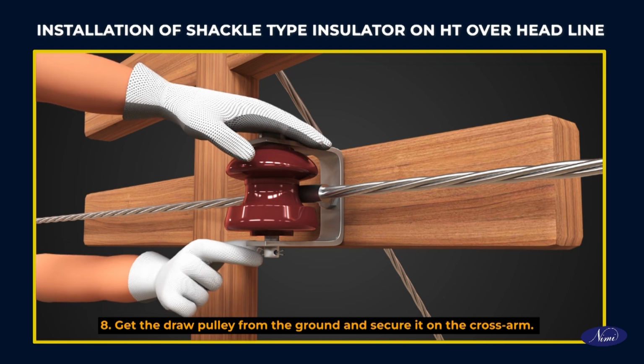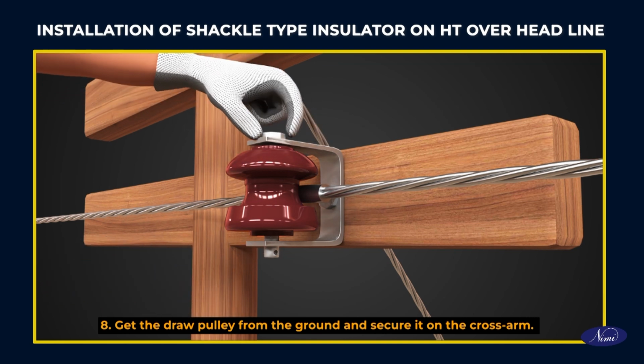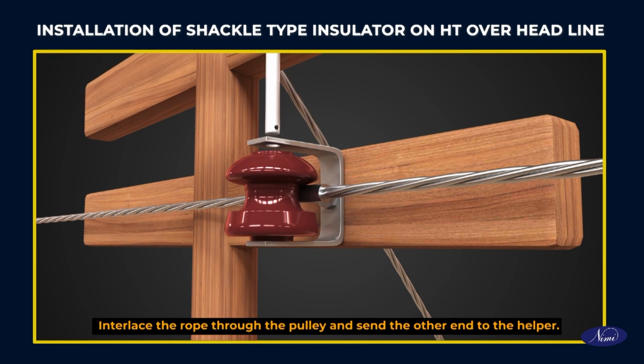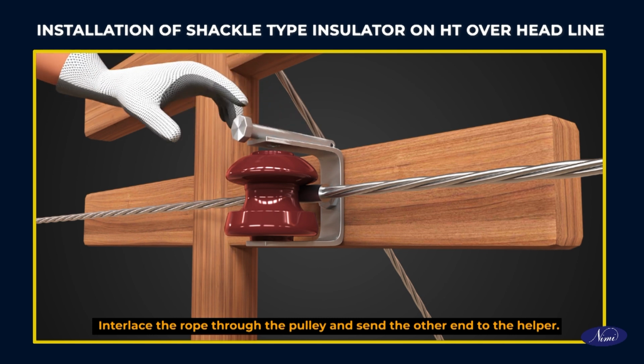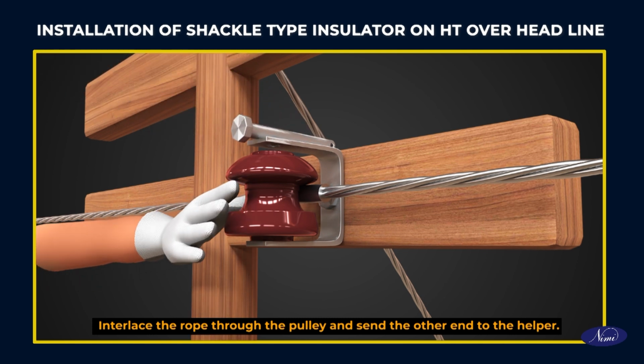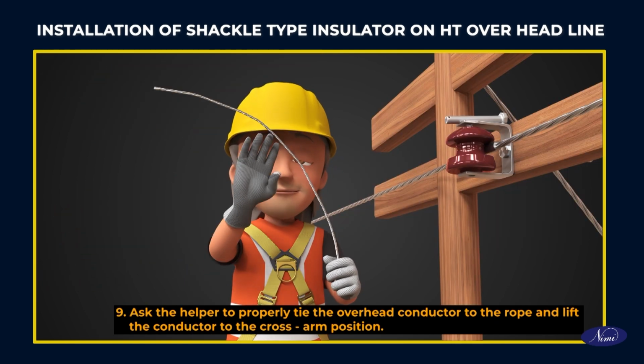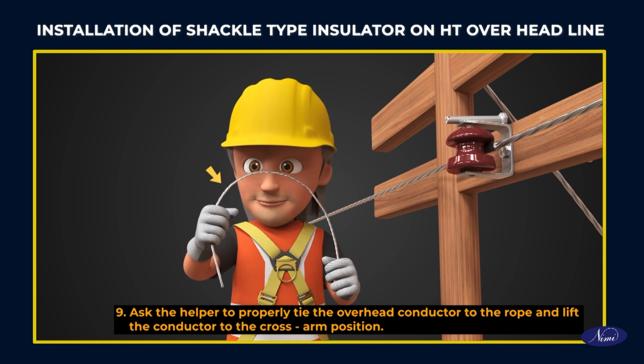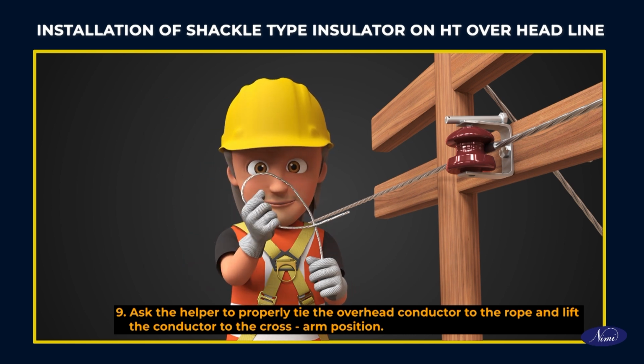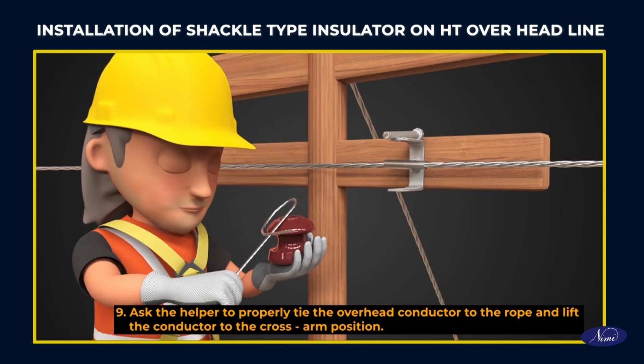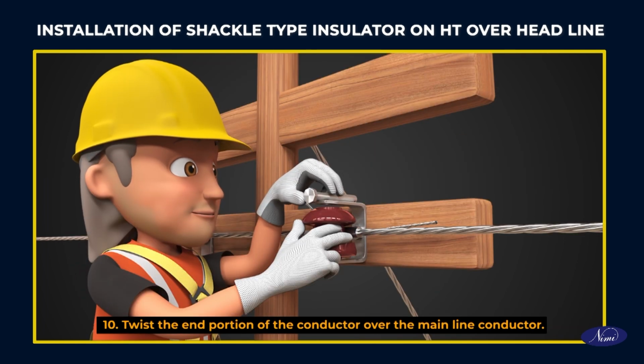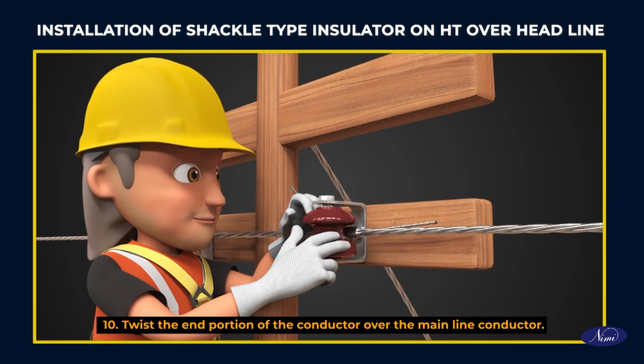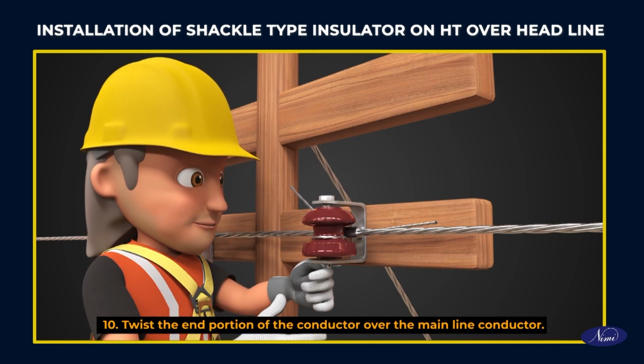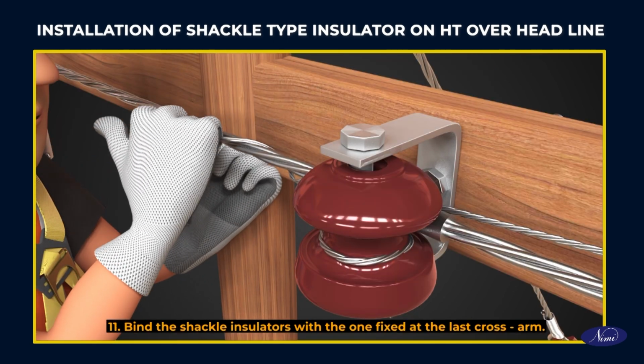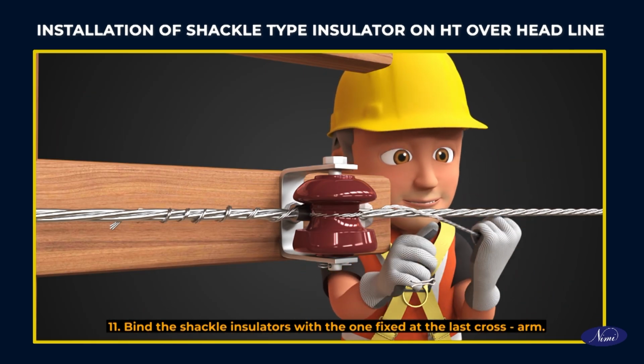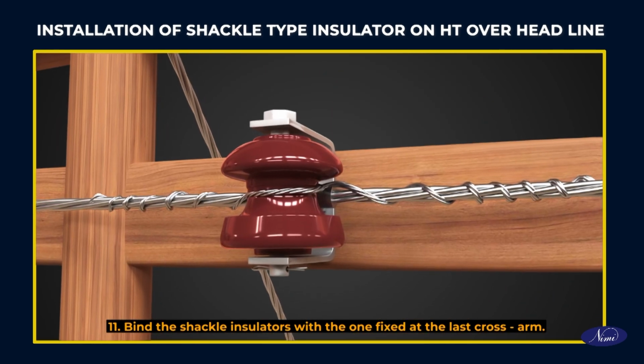Get the draw pulley from the ground and secure it on the cross arm. Interlace the rope through the pulley and send the other end to the helper. Ask the helper to properly tie the overhead conductor to the rope and lift the conductor to the cross arm position. Twist the end portion of the conductor over the main line conductor. Bind the shackle insulators with the one fixed at the last cross arm.